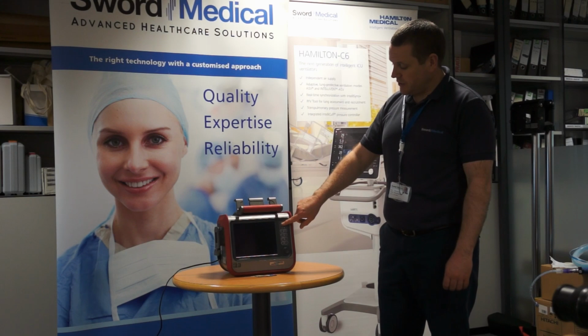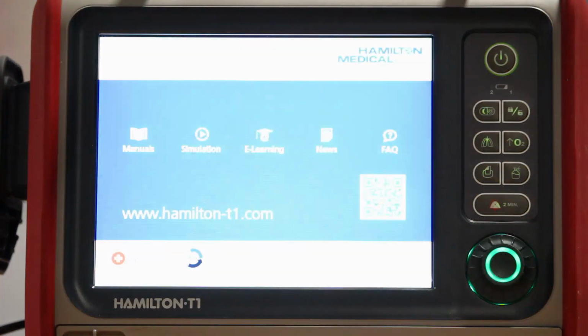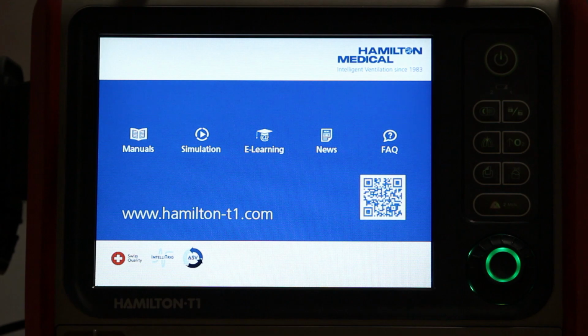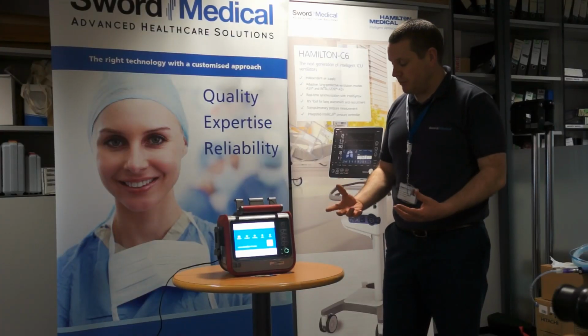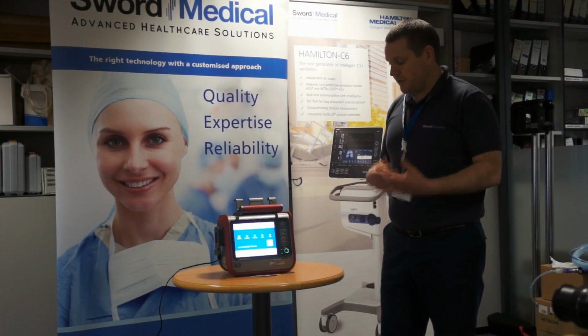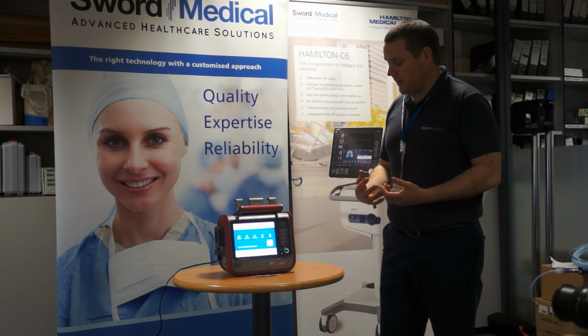So now I'm going to switch it on, and when I do switch it on, what the ventilator does is it runs through an internal self-diagnostic. So you'll see a small bit of text come here saying self-test. So it's testing all its internal components, its circuit boards, the turbine, the alarm, all those kind of things.